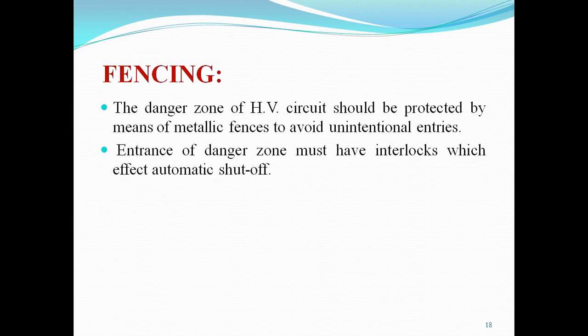Fencing. The danger zone of a high voltage circuit should be protected by means of metallic fences to avoid unintentional entries. The entrance of the danger zone must have interlocks which effect automatic shut off. You will also find the difference between other laboratories and the high voltage laboratory. There is metallic fencing in the high voltage laboratory. Outside there is a control area, and on the other side there are the testing transformer, impulse voltage generator, and DC test setup, and the equipment under test is put to the side. So the fencing is also required in the high voltage laboratory.